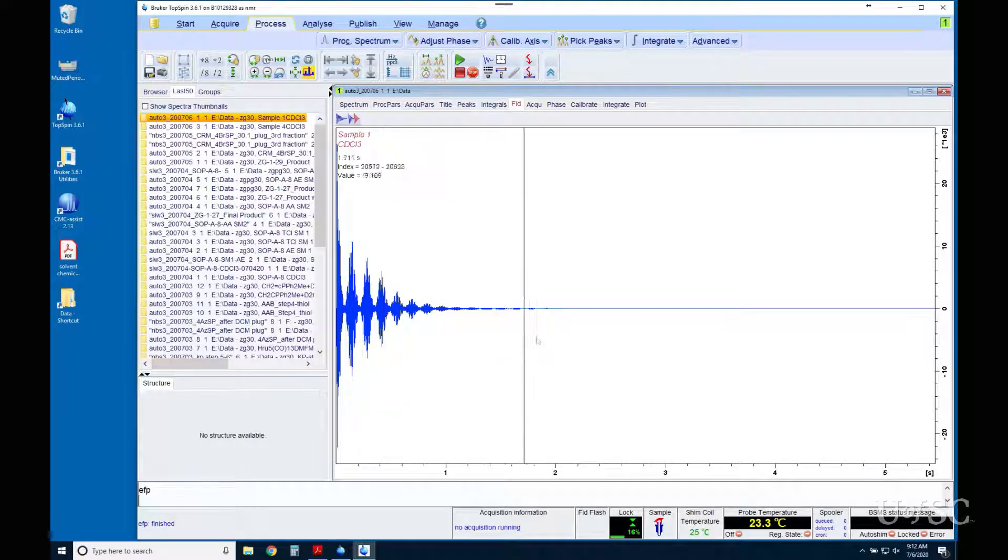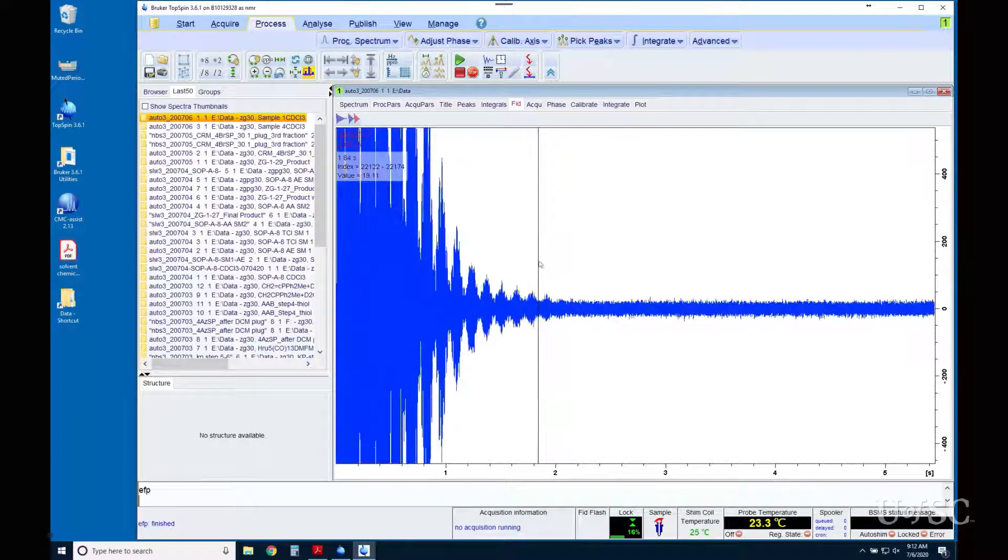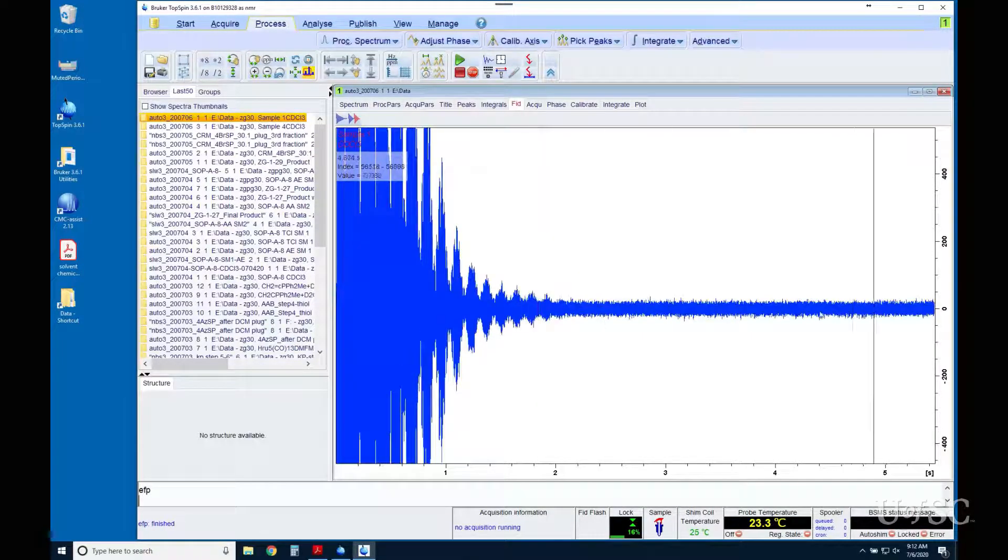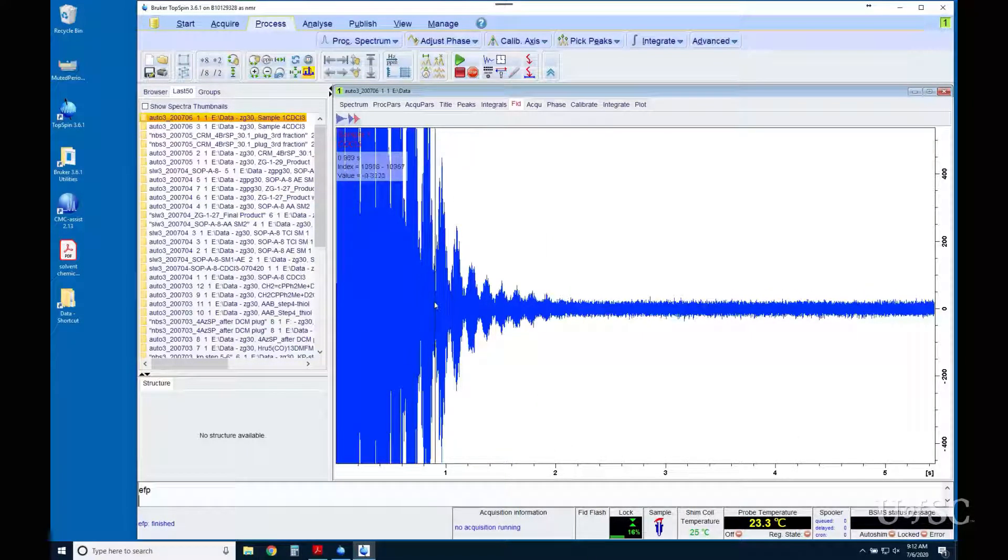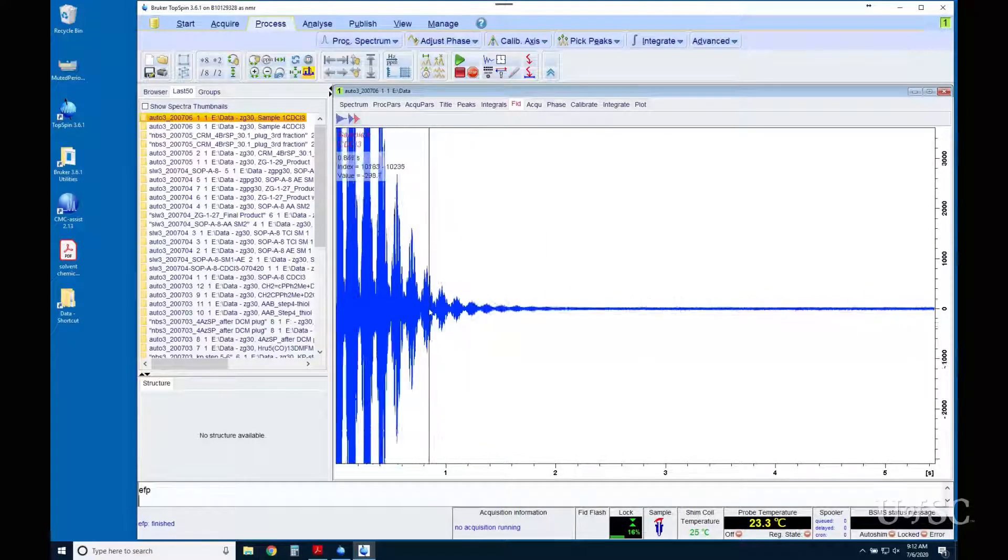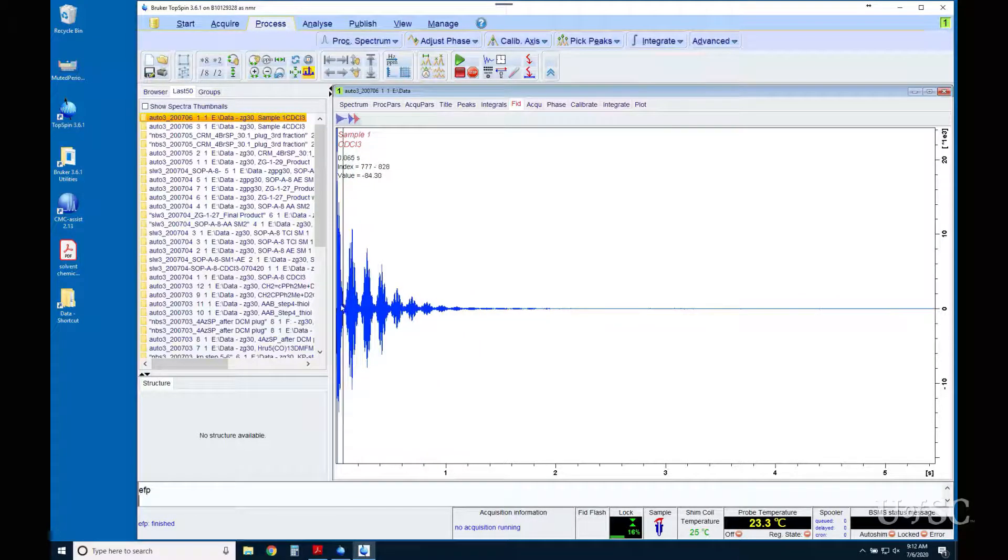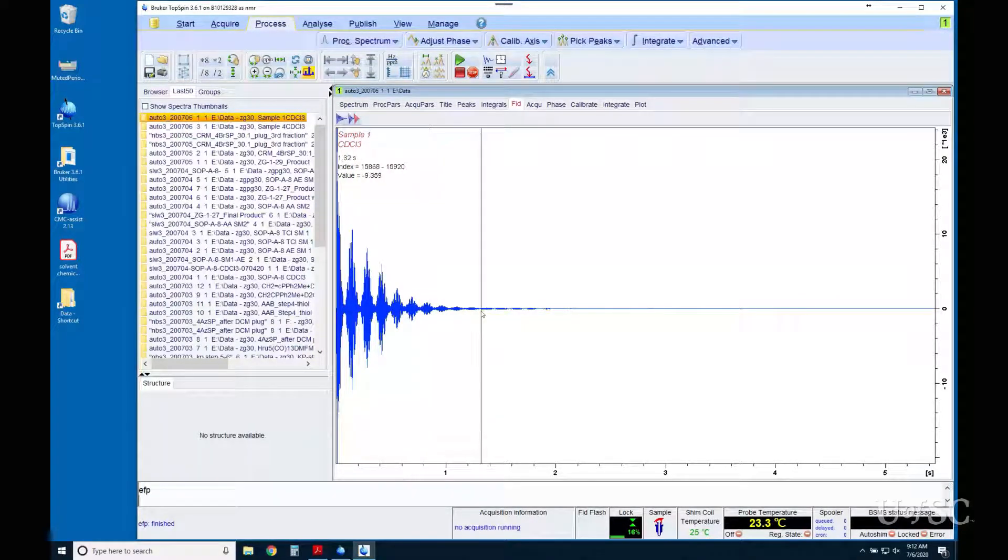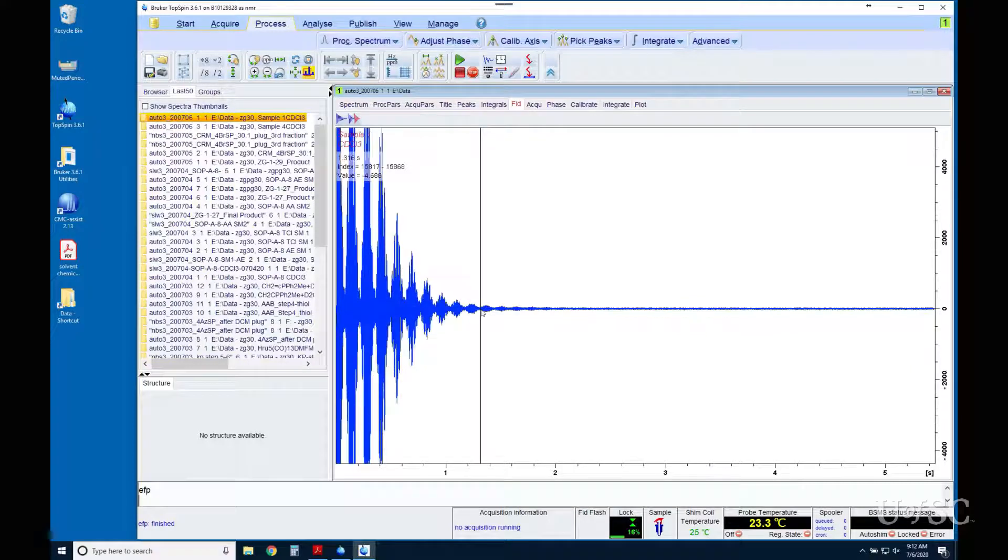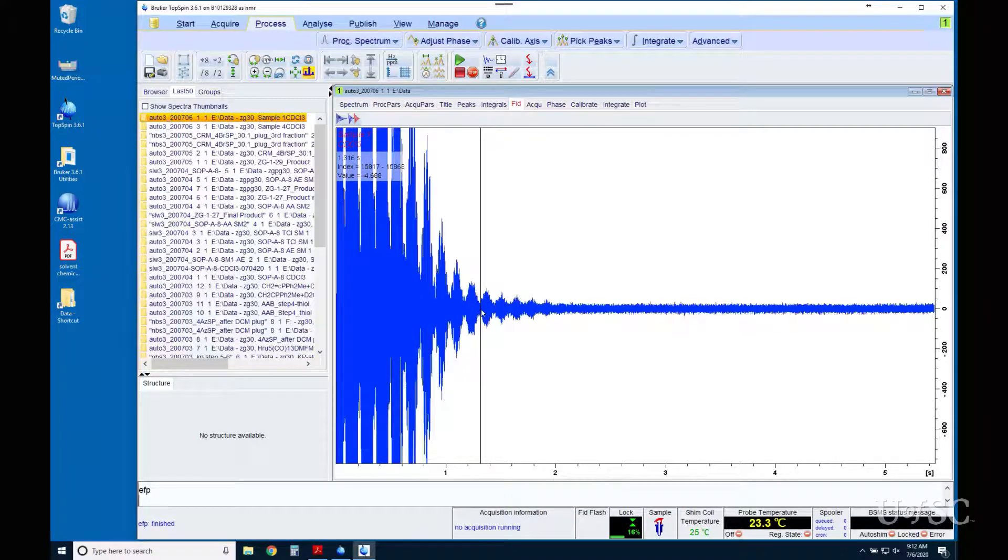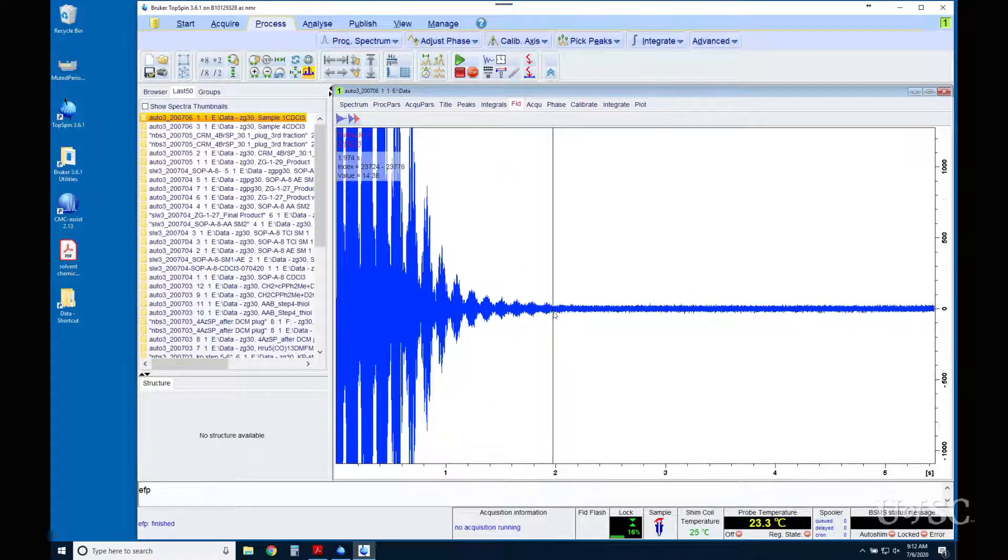Since noise is constant over the acquisition time, the signal-to-noise ratio, often considered the sensitivity, is better in the front of the FID than at the end. However, the longer we collect the NMR signals the better the exact frequencies are determined, so the line width information is at the tail of the FID.